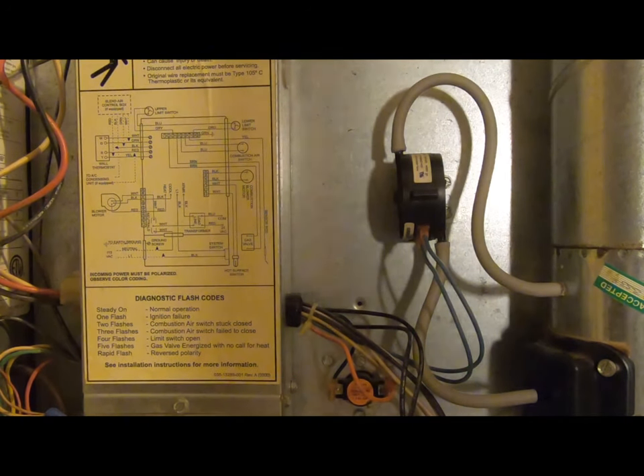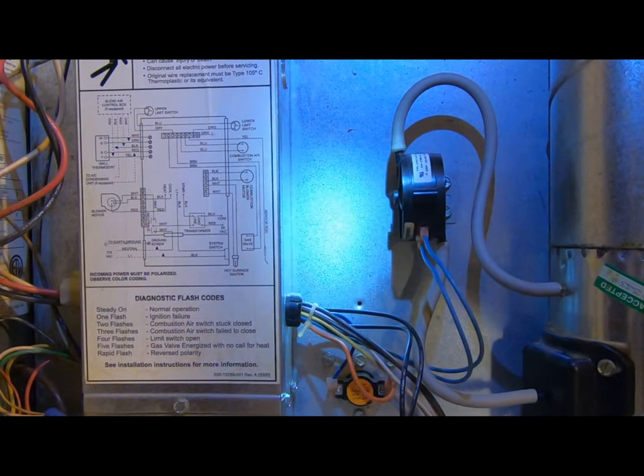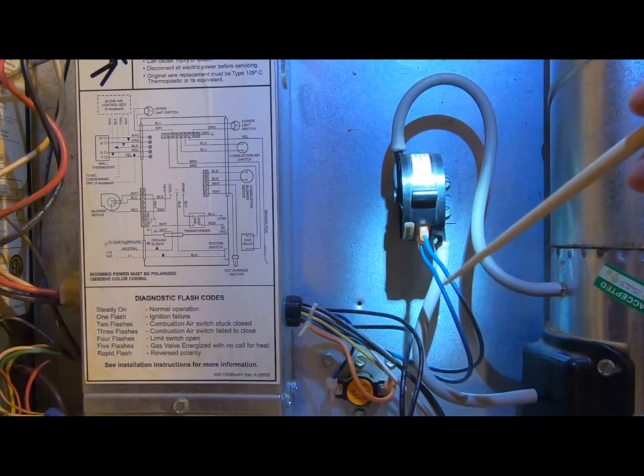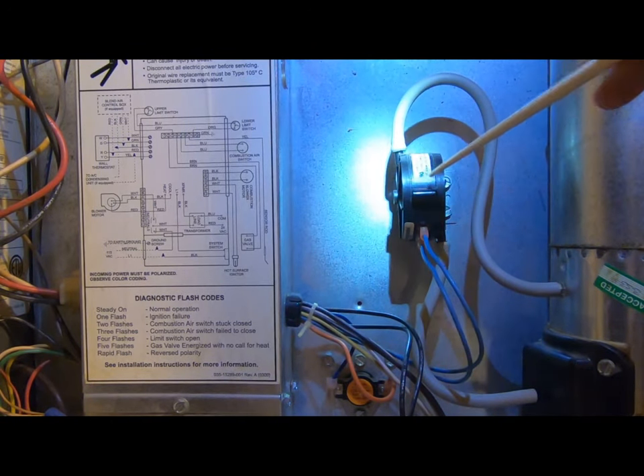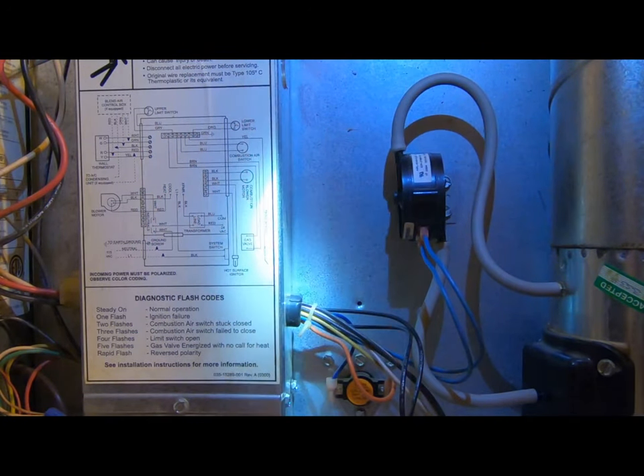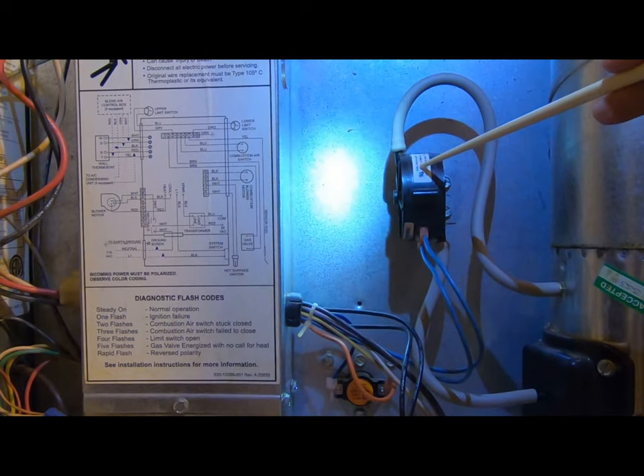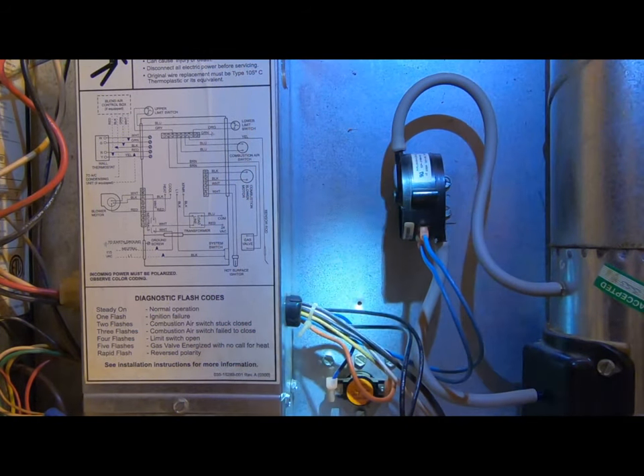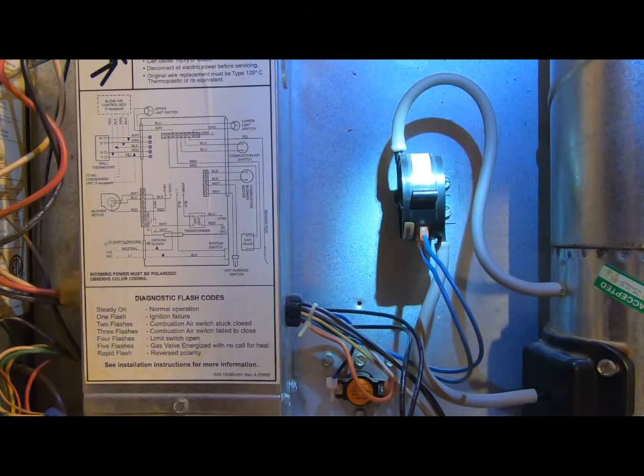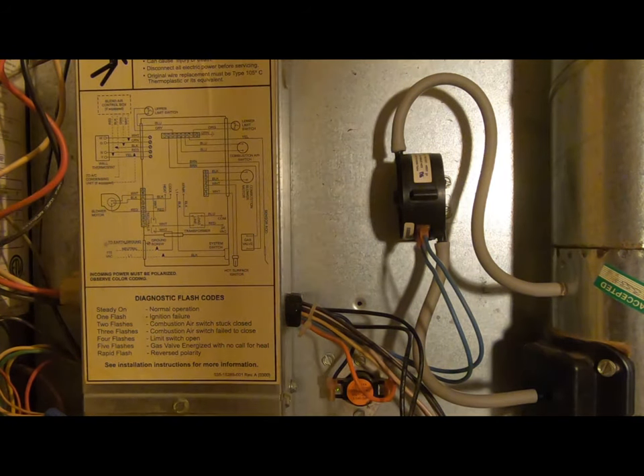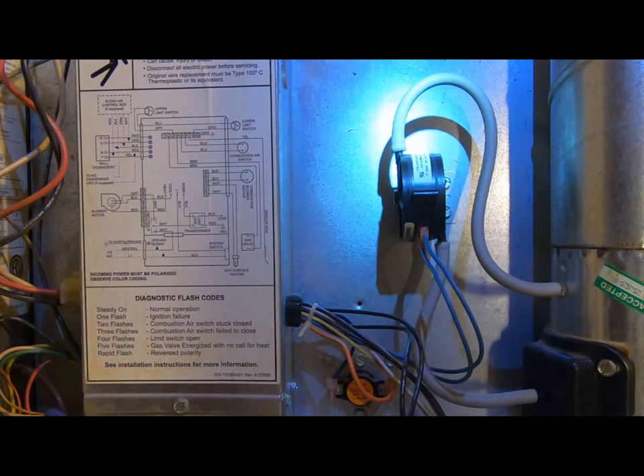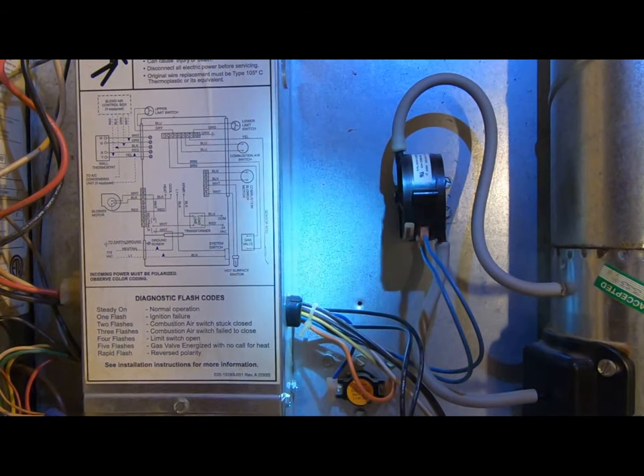Combustion air switch failed to close. This is the only thing with two blue wires going to it, so it is your combustion air switch, which can be confirmed by finding your installation manual. I had to look it up on the internet, but the part number here and here match what's in the manual as combustion air switch. And I'll show you how to test it.